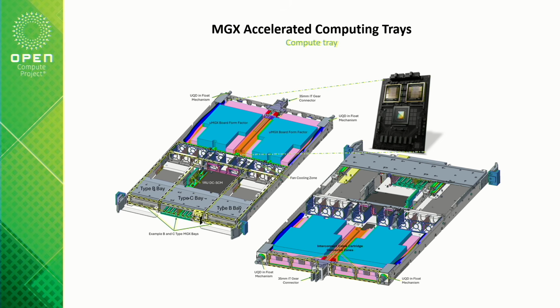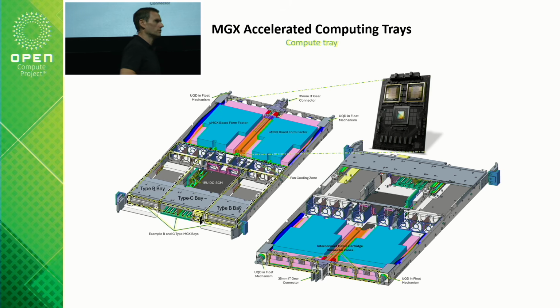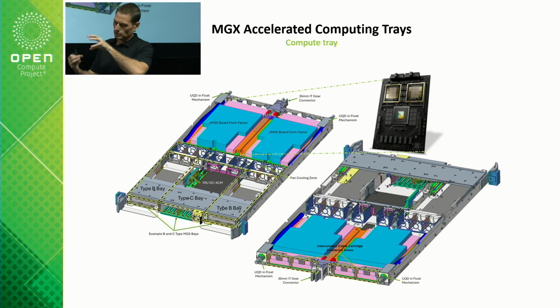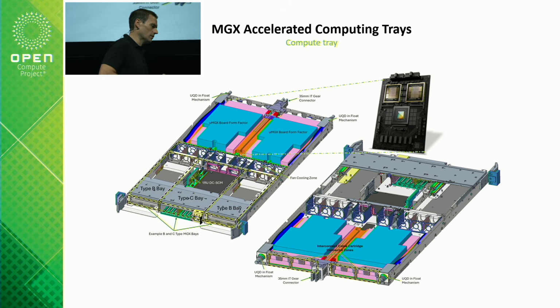On the back of the tray you'll see the UQDs, universal quick disconnects. That's also an OCP standard we leveraged. We took that and wrapped a floating mechanism around it. I talked about how the electrical connectors need to float to find their final home, well the liquid connectors need to do the same. So despite all the high precision machining we did on the manifold, we still need some radial and axial freedom in that float mechanism for those connectors to find their final position and have a reliable, high quality seal.